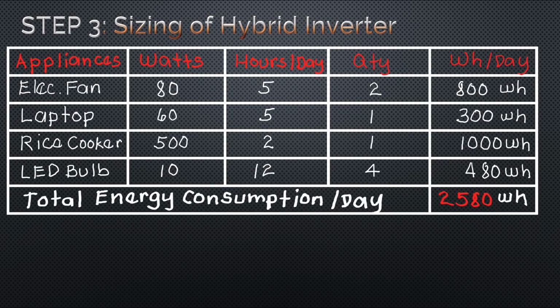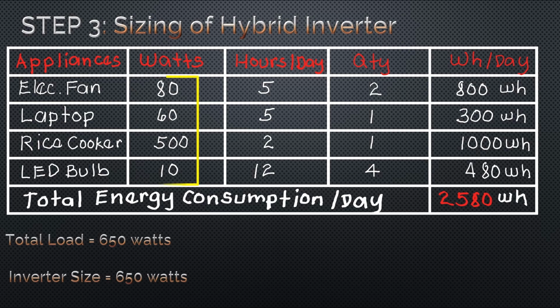In the computation of inverter capacity, there are different methods used, each with its own reason and purpose. This time, I will show you the different methods. I will use the load profile in our example setup. For example, some installers use the total load in the house as reference. In this load profile, the total load is simply the sum of the wattage of the appliances. So the total load is 650 watts. Therefore, the size of the inverter will also be equal to 650 watts.